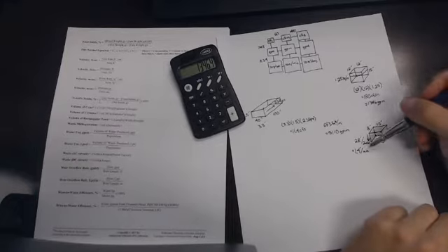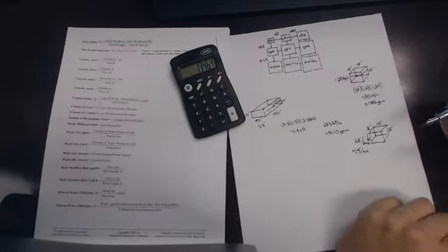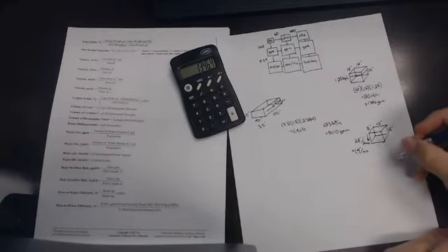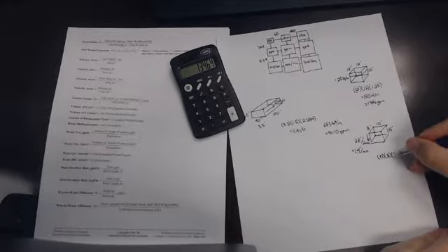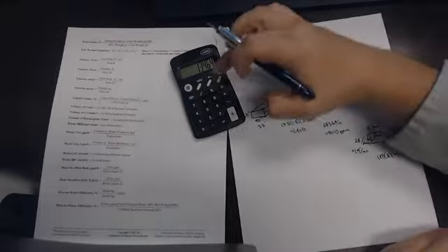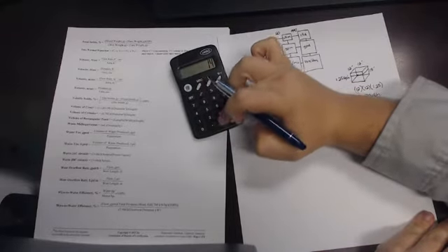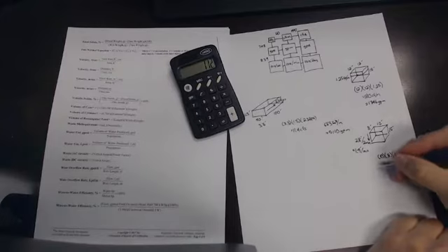So we're looking for gallons per minute, and we have it in 1 minute. Now we just have to calculate the cubic foot per minute flow rate. So you take the 10 foot times the 8 foot times the 1.4 foot per minute. Let's see what that gives us. 10 times 8 times 1.4, we've got 112 cubic foot per minute.